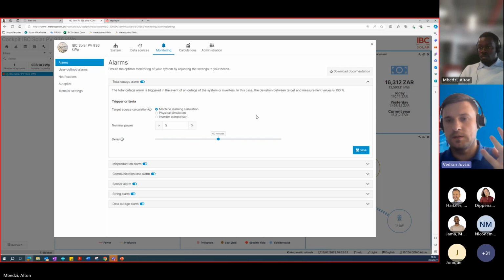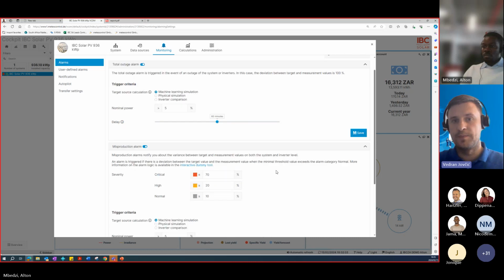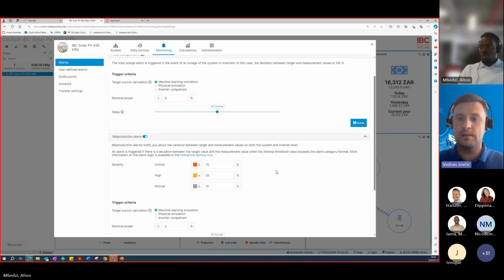But you, as the technician or O&M manager, know this is due to the shadowing event. After 2 weeks, VCOM understands and sees this is a typical behavior of the system - 14 days in a row with the same event means this is a specific behavior of the system. So from day 15 or 16, you will not get this alarm anymore, because VCOM understands it's due to a specific situation of the system. That's what's meant by machine learning simulation: understanding the behaviors and specificities of your system so that you're really only notified by the alarms you have to consider.